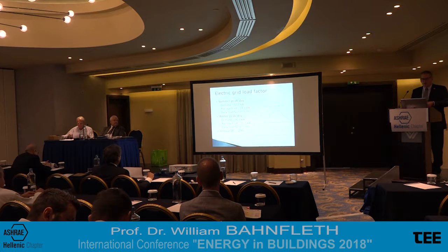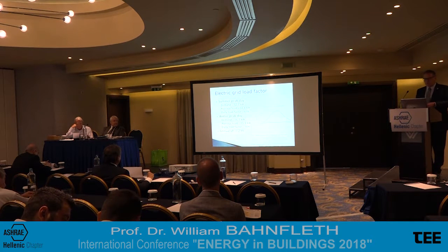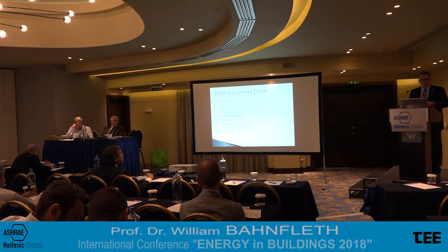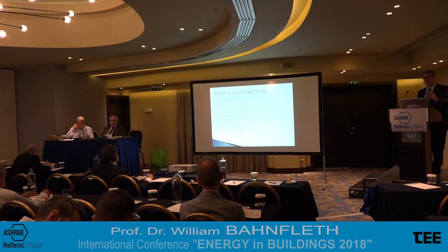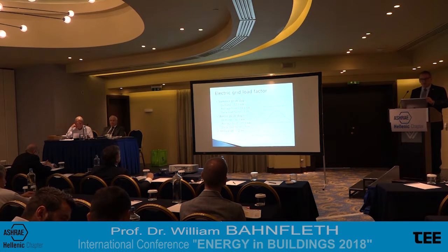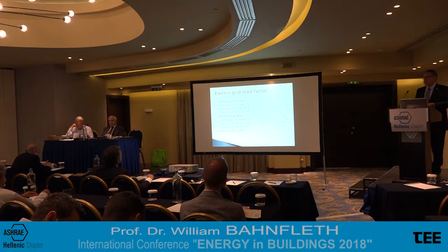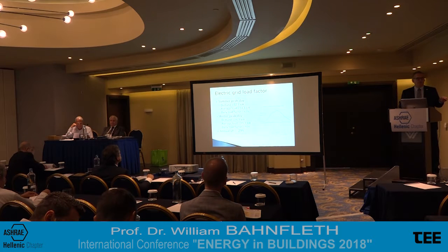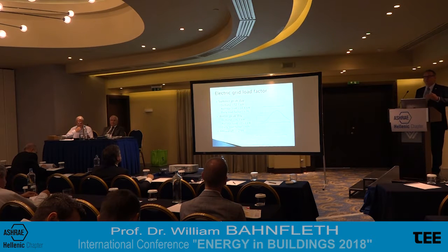A summer day load factor for Pacific Gas and Electric for one of its types of rates, shown there in the figure, is about 63%, while in the winter it might be 90%. But the annual load factor, the capacity you would have to meet, the average annual load compared to the peak load for the year, is only 29%. So that means that the people who buy electricity from that utility have to pay for 3 kilowatts of generating capacity for every average kilowatt of capacity that's actually needed to meet the load. So to the extent that you can move that peak in the direction of the average, rates should go down.